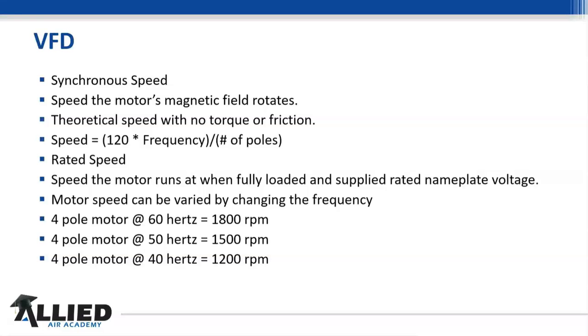You get rebates back for certain buildings. Well, we had to do all this, and we had to put these drives on there to reach all these new standards. And this is one of the ways, one of the simplest ways you can do it, is just drop the speed of that fan motor. And you'll notice a lot of times the amp draw, especially on your bigger units, goes down quickly.